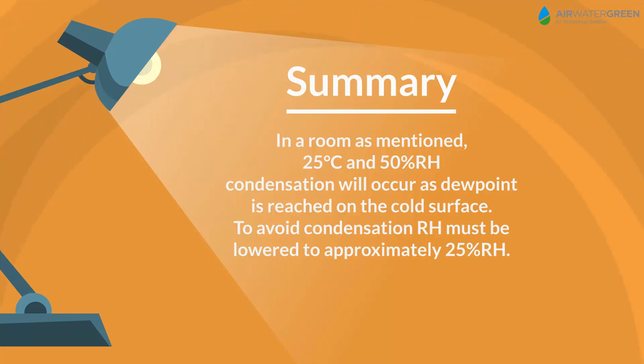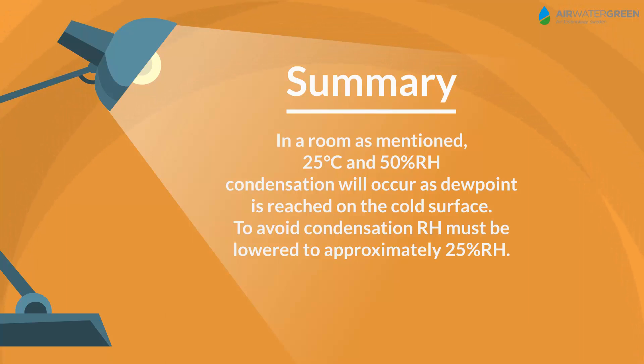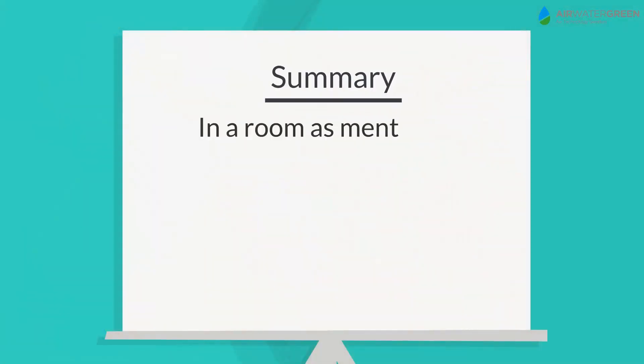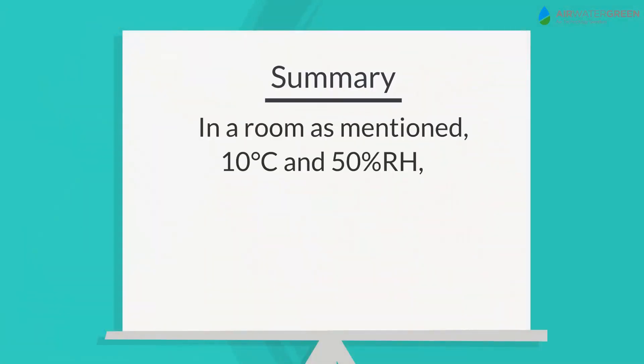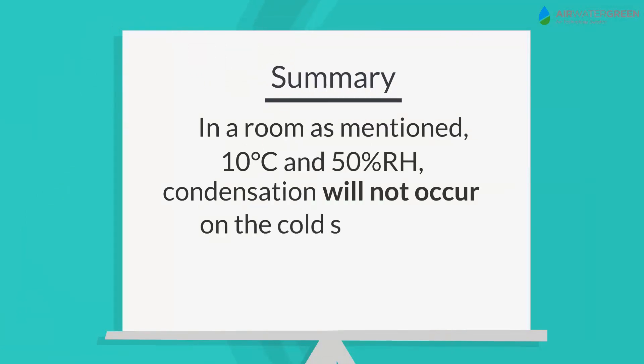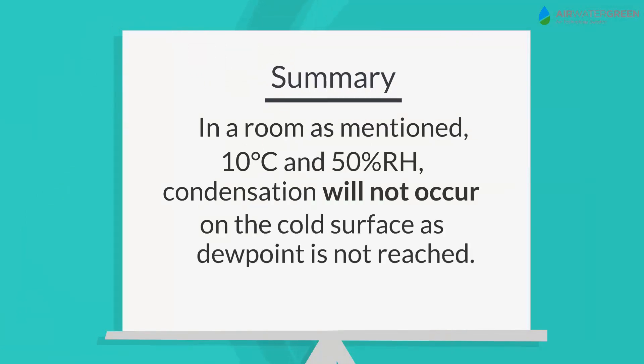To avoid condensation, relative humidity must be lowered to approximately 25%. Alternatively, in a room at 10 degrees Celsius and 50% relative humidity, condensation will not occur on the cold surface as the dew point is not reached.